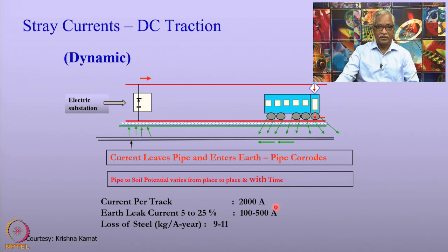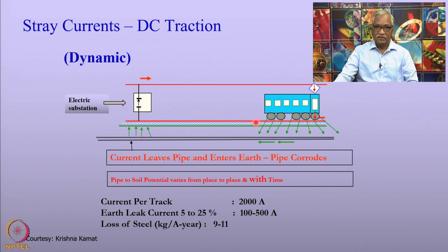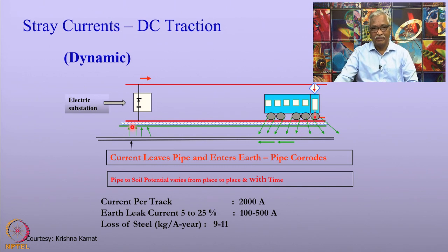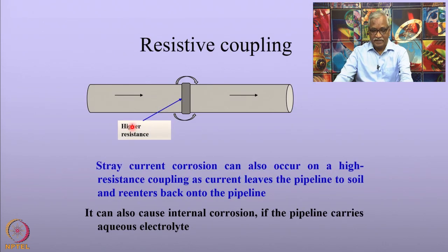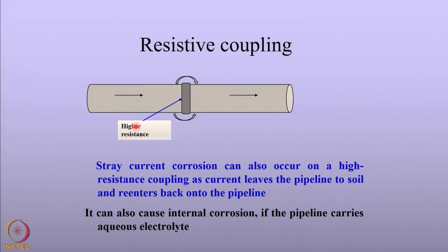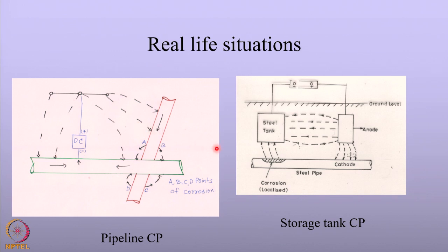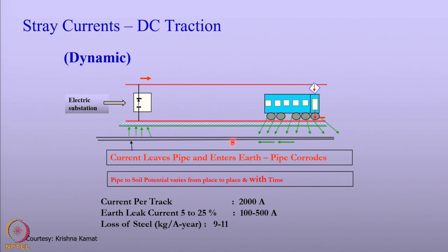With this kind of current, about 9 to 11 kg per ampere year of dissolution can happen at that location, leading to very quick leaks in the pipelines. This kind of corrosion is dynamic in nature because it occurs only when the train passes through, and other times it does not happen. This is different from what was seen earlier — static stray current corrosion, where corrosion occurs all through the day.